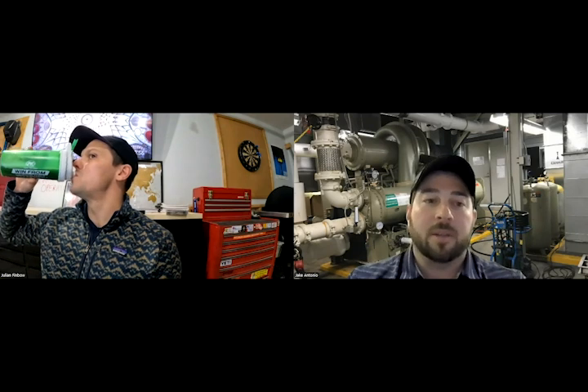I've seen some literature where it's 410A and it says 150 psi, which doesn't make any sense to me because the refrigerant operates at a lot higher pressure than that. But when I worked on York VRF equipment, it specifically stated that you had to pressure test the whole system at 600 psi for 24 hours and it needed to hold. I know it's a high pressure, but they want to verify that the whole system can maintain 600 psi. It's probably going to run a maximum of about 500, maybe up to 550. But they recommended that in the literature.